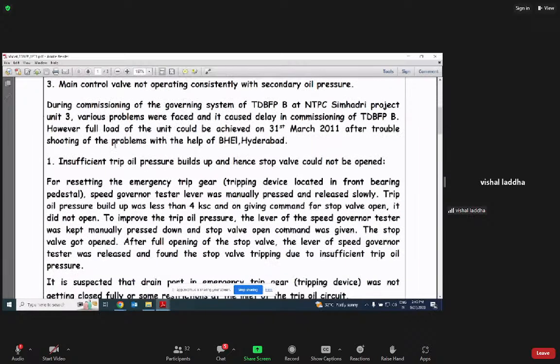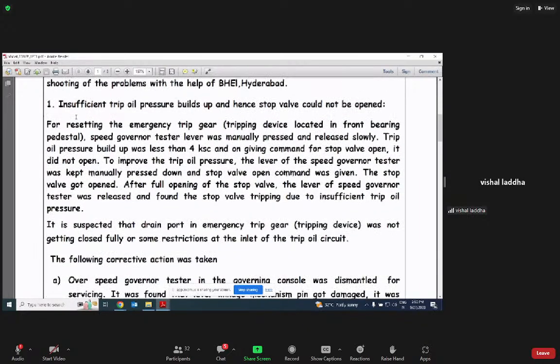So what was the reason? Insufficient trip oil pressure build up, and hence the stop valve could not be opened. For resetting the emergency trip gear, the tripping device located in front of the bearing pedestal, the speed governor tester lever was manually pressed and released slowly. Trip oil pressure build up was less than 4 ksc, and on giving command for stop valve open, it did not open. To improve the trip pressure, the lever of the speed governor tester was kept manually pressed down, and the stop valve open command was given. The stop valve got opened.